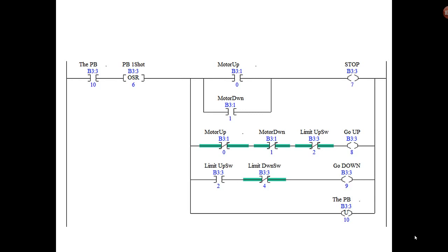To save you the trouble of right-clicking again to toggle it back off so you can toggle it back on again, we use the logic to untoggle what you just did. Which means that B3:3/10, when you toggle it on, it is going to turn right back off within this rung logic, but not before it decides whether to stop, go up, or go down.